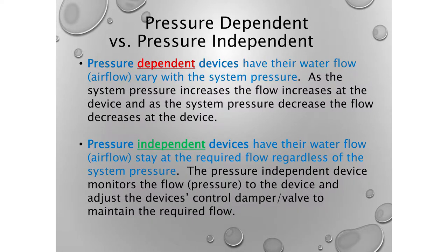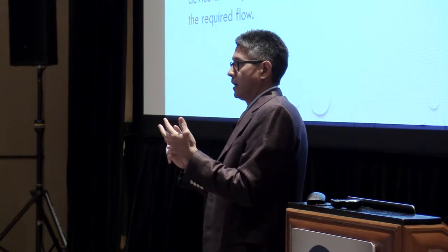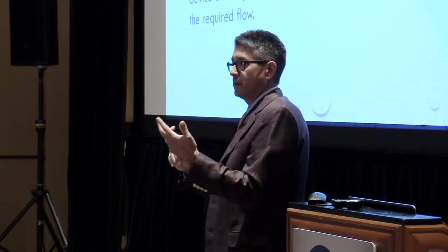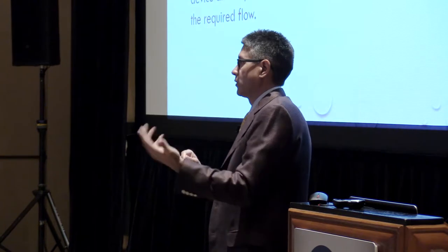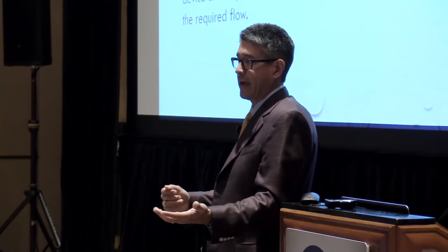Pressure-dependent devices versus pressure-independent devices. That's probably one of the biggest challenges we're seeing right now in our industry. Understand that with a pressure-dependent device, if the pressure changes on the inlet of that water valve or that VAV box, the flow will change accordingly with it. So pressure goes up, flow goes up; pressure goes down, flow goes down.